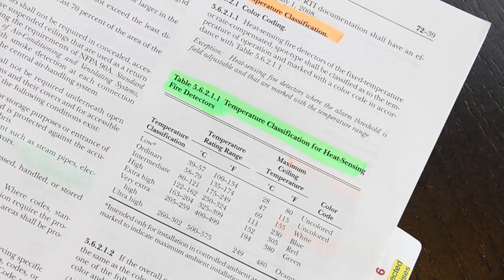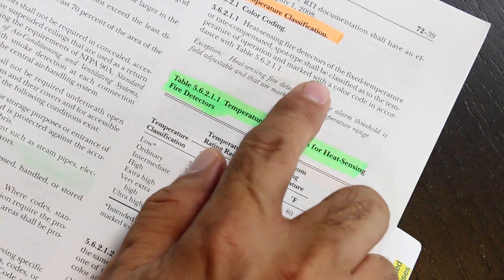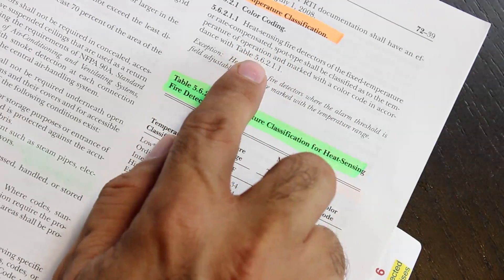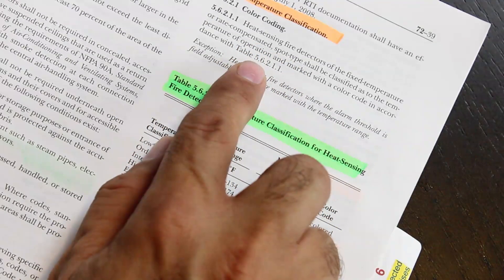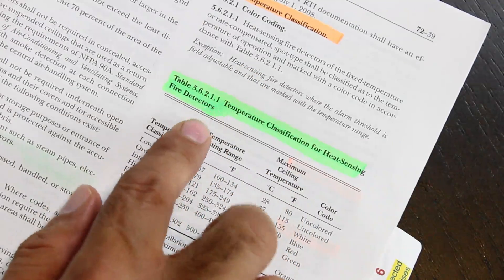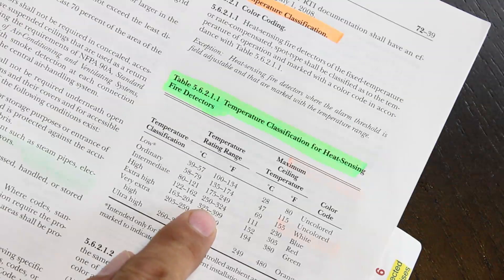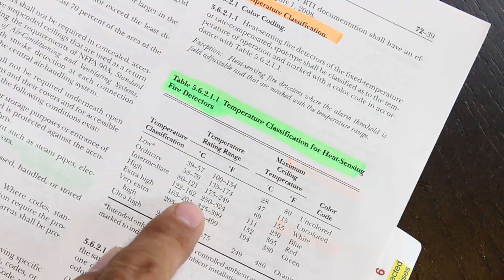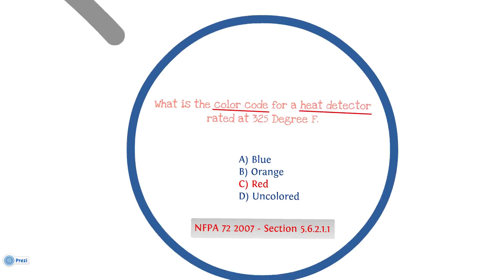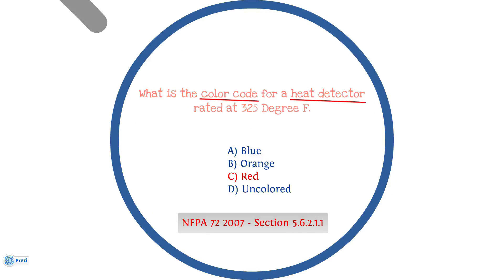Then heat sensing fire detectors of the fixed temperature spot type shall be classified as temperature of operation and marked with the color code in accordance with table 5.6.2.1.1. Here is the table. We said, what's the 325? We go for 325. 325 is color red. Coming back to the question, the answer is C, red. We find that in section 5.6.2.1.1 in NFPA 72, 2007 edition.